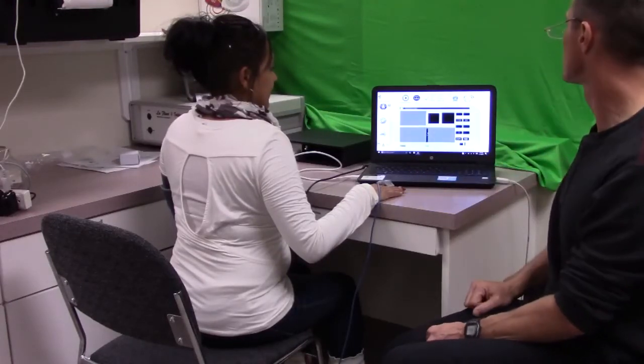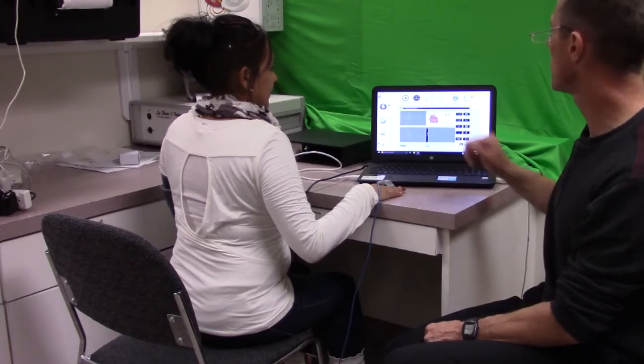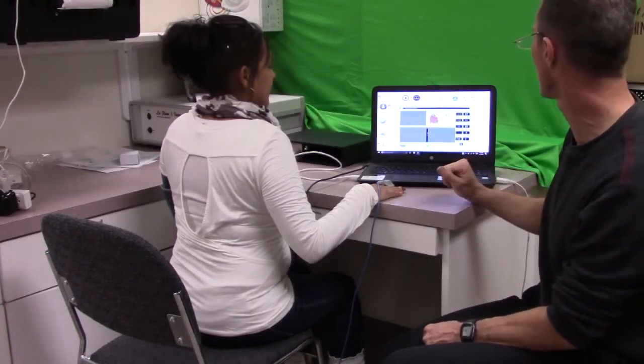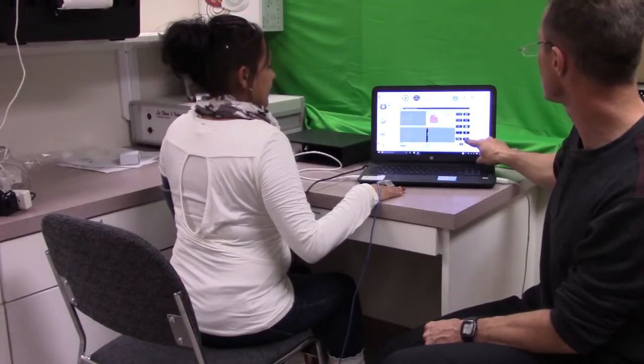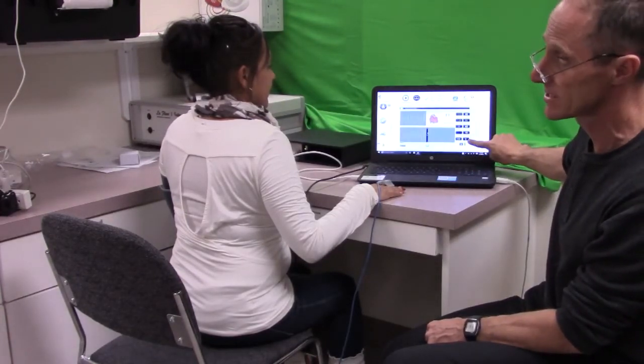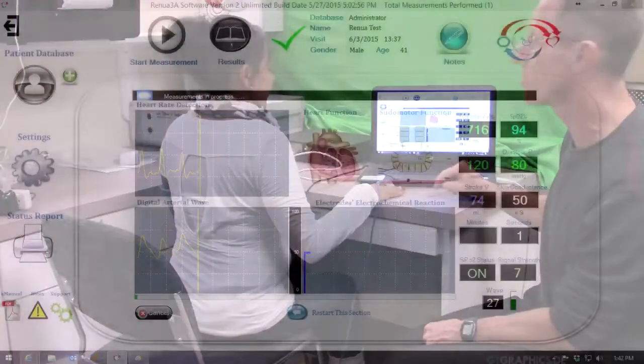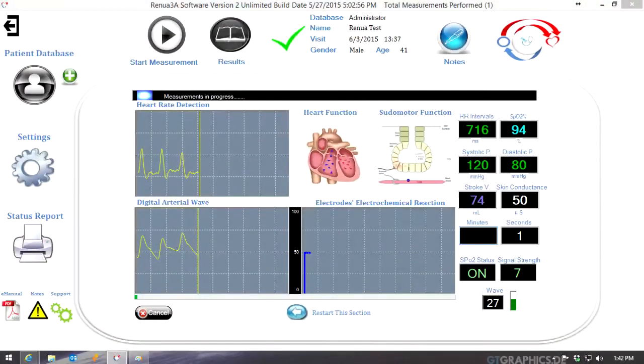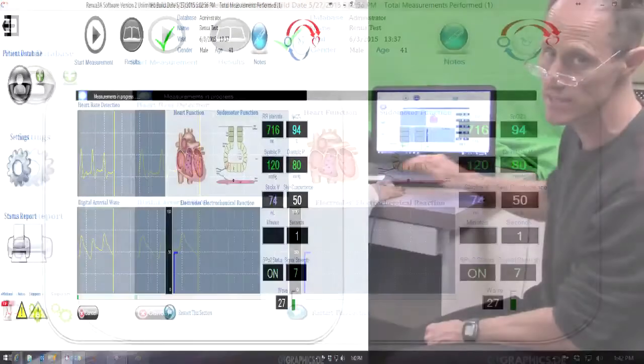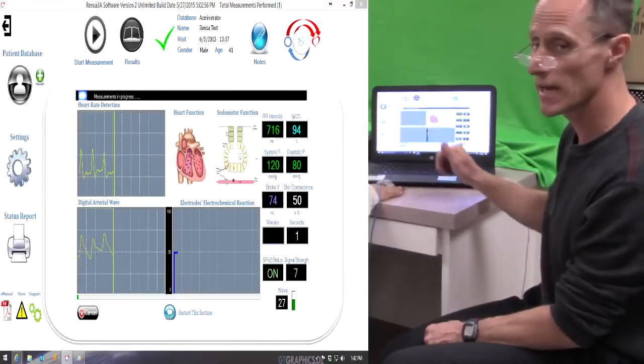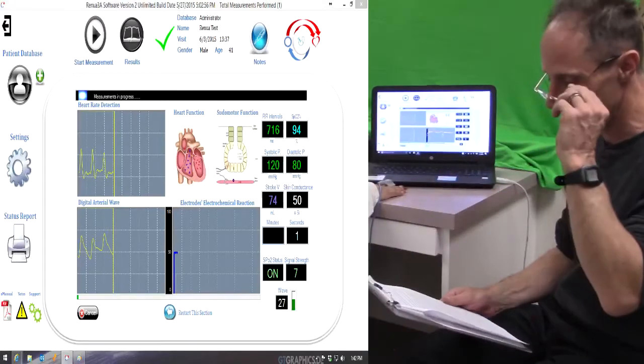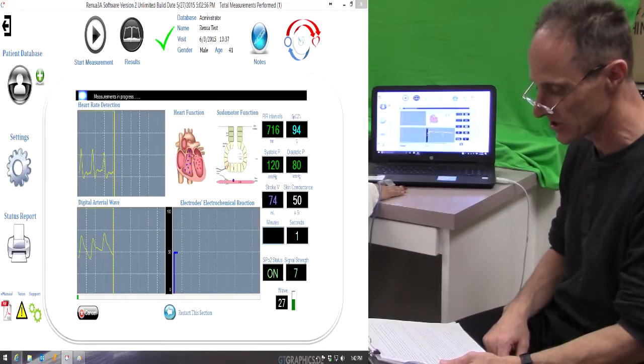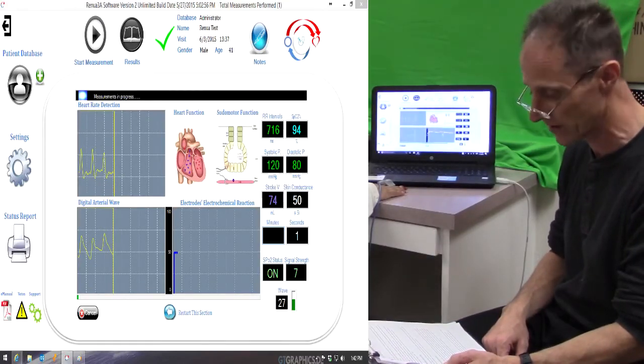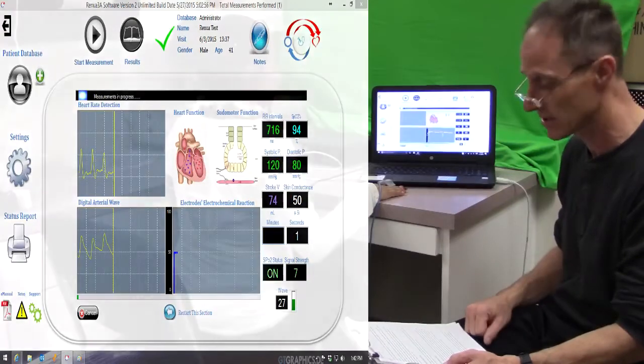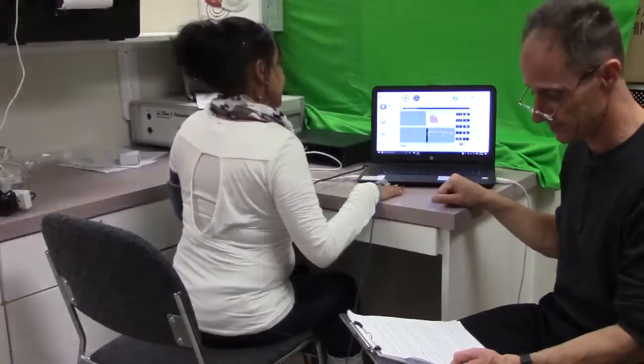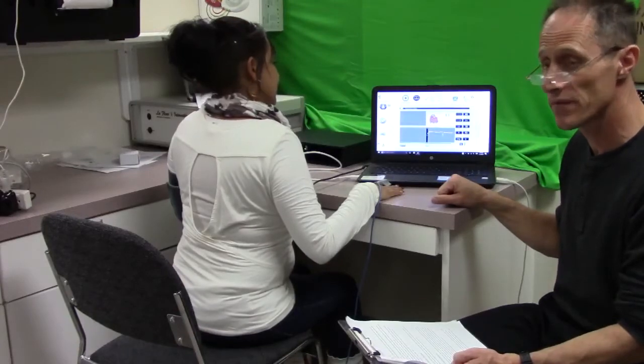Phase 2, baseline recording. This is our baseline, the second phase of the test. What I'm going to do is make sure that my signal strength over here is a 3 or higher. If it gets any lower than a 3, then you might have to redo the test, because that means your pulse oximeter is not receiving a good signal from the patient to the ANS box. So we're at the baseline recording, and the baseline measures the heart function, electrochemical reaction response, and sudomotor function while the patient is relaxed. We'll go ahead and let this finish out, and then we're going to be moving to phase 3.